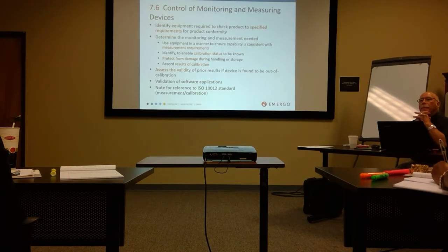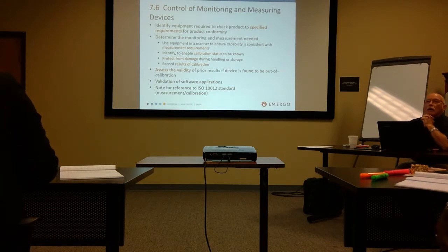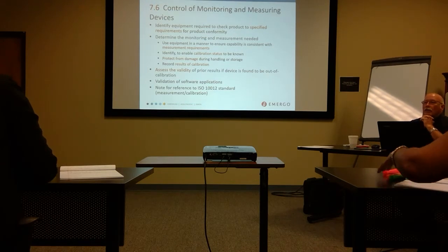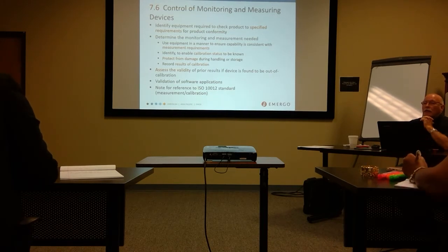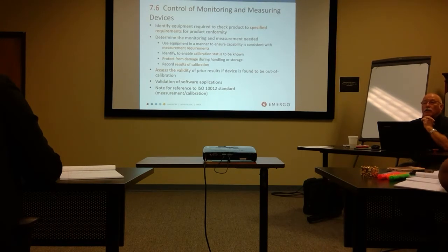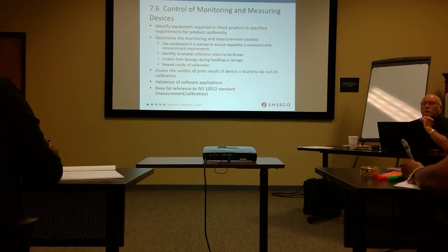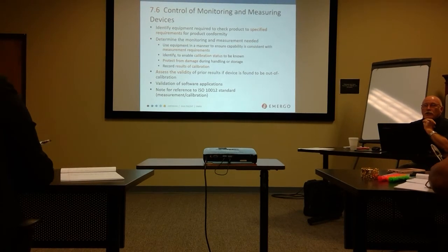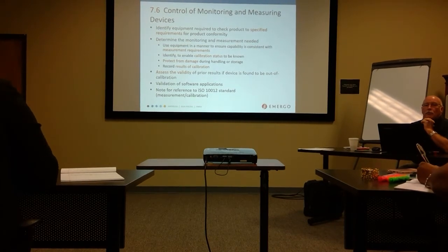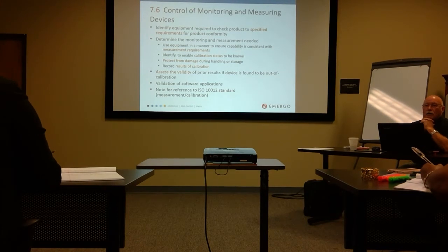Yes, ma'am. You said on the calibration log you want frequency, how, and who. What is the how? The test method, or if it's internal or external? If it's all external, then you don't need to worry about it. You don't need to cite their test method. You don't even need how unless you do it internally. So how is only applicable, and how is where you would cite the procedure number if you did it internally. If they're all external, don't worry about it. I would suggest that unless you have a metrology group and have a really big need for this, I would recommend you outsource it.